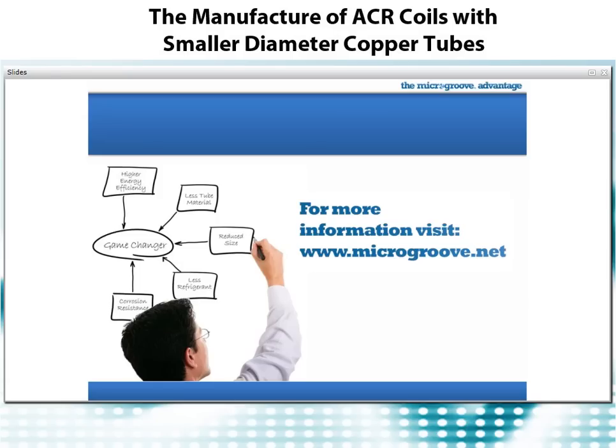Question: what is the effect of the expander on the micro-grooves inside the tube? If we're talking about mechanical expansion, as I presented today, it does have a reduction effect on the micro-groove — it is not completely wiped clean, but there is some reduction at the top. Making an educated guess at the reduction in overall height, it's probably about 30% of the micro-groove that would be eliminated.